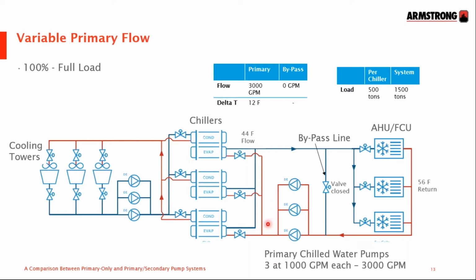and producing... The chillers will be controlled to produce a 44-degree leaving chilled water temperature, passing through the air coils in the air handlers, where they'll accept heat from the zones being served, which will warm the water up to 56 degrees Fahrenheit and then return back to the chillers. As long as the minimum flows to the chillers are not breached, the bypass valve remains closed during normal operation.